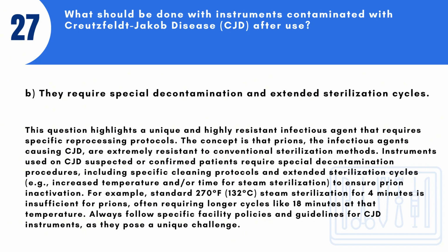Answer: B. They require special decontamination and extended sterilization cycles. This question highlights a unique and highly resistant infectious agent that requires specific reprocessing protocols. The concept is that prions, the infectious agents causing CJD, are extremely resistant to conventional sterilization methods. Instruments used on CJD suspected or confirmed patients require special decontamination procedures, including specific cleaning protocols and extended sterilization cycles, e.g., increased temperature and/or time for steam sterilization, to ensure prion inactivation.